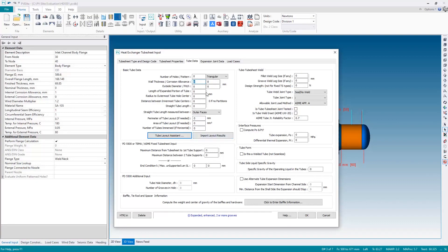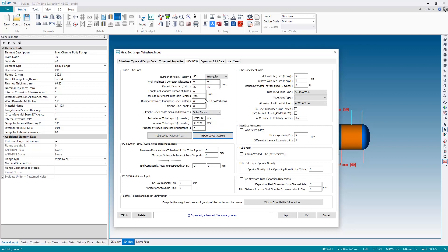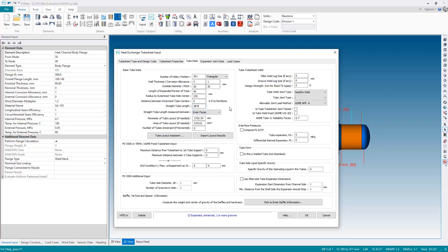And then, back in PV Elite, in the tube sheet input, I can just hit the import layout results and that will fill in the majority of the information required on here. Which just leaves me to specify a few more pieces of information. So a 3 mm wall thickness, let's have a 1 mm corrosion allowance, the expanded portion of the tube, 40 millimeters, and the straight tube length. Well, I'm going to measure that between the inner faces rather than the outer faces. And the distance between the inner faces, the straight tube length, is the same as the length of our main shell, which was 2.87 meters. And that's it for the basic tube data.